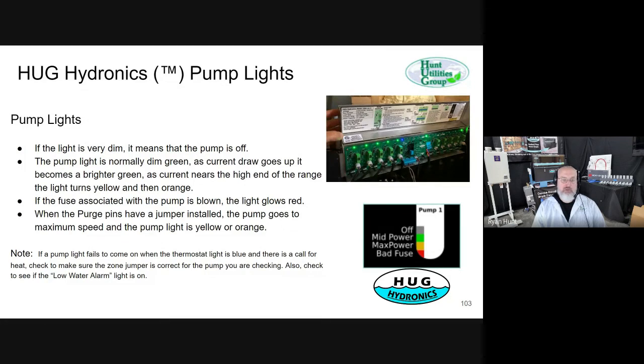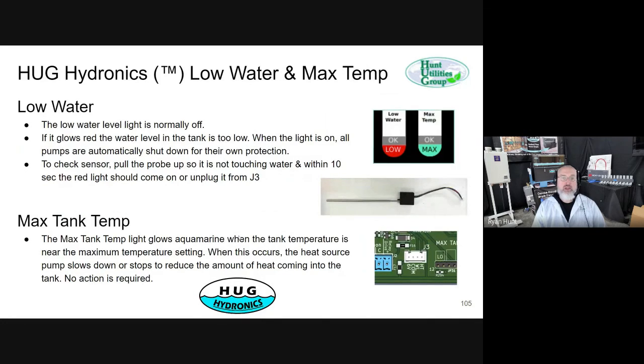As I mentioned before, we've never had a fuse blow. We've got the low water sensor. When the water level gets low, it'll turn everything off. It'll stop all the pump flow. You've got to have enough water to keep it safe to run the water heater, so we turn the water off when it gets low.